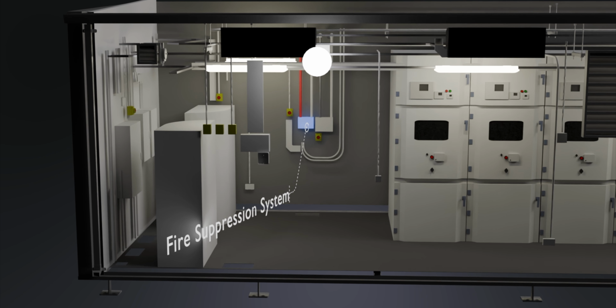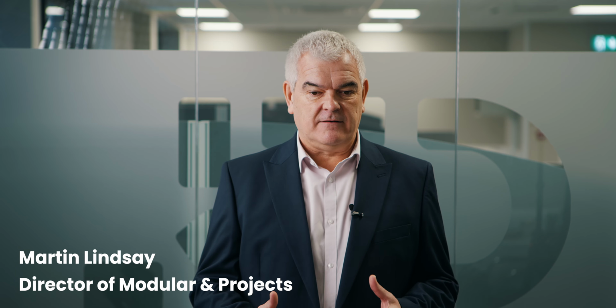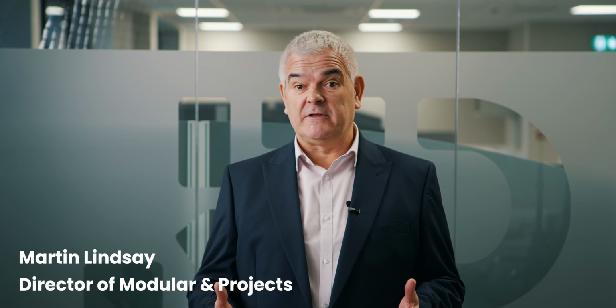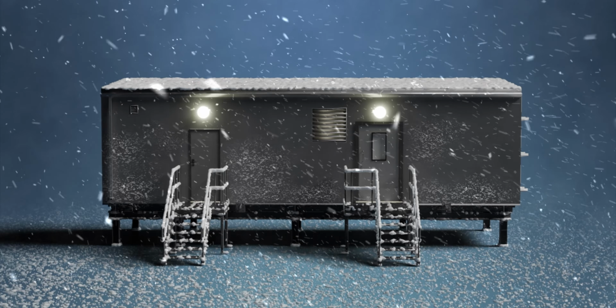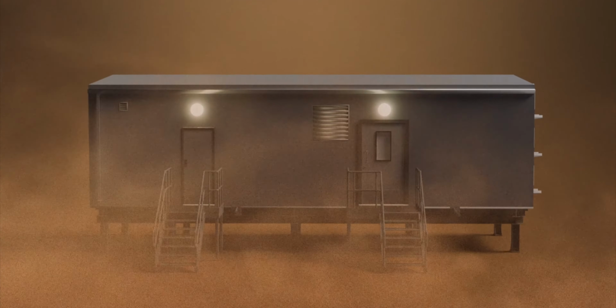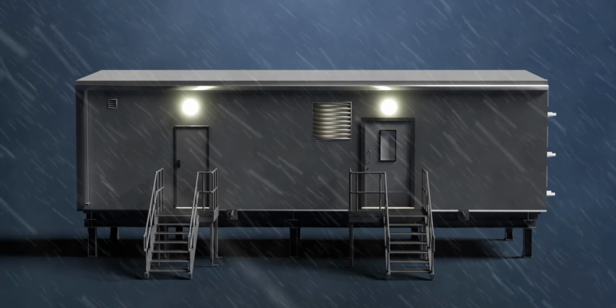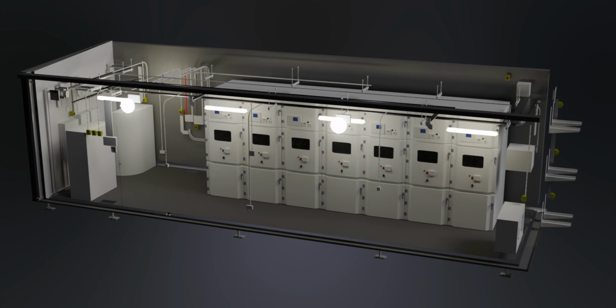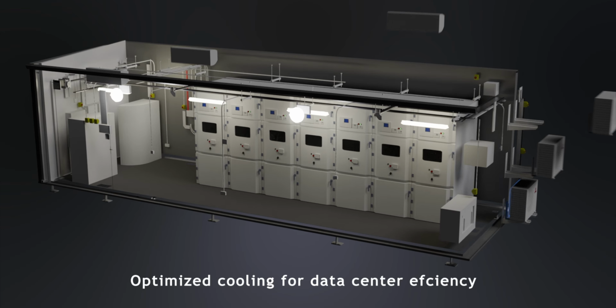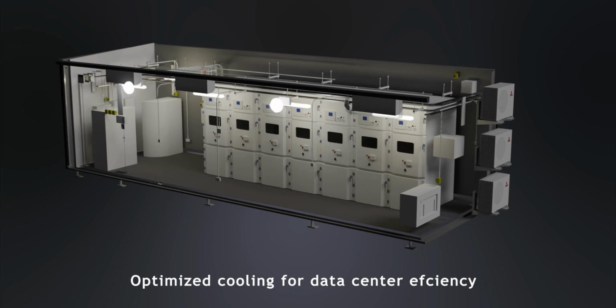So some of the considerations we have when designing a modular solution is to think about the environment that we're going to use that solution in. So what countries are going to be based, what's the temperature, what's the humidity, what are the conditions like. Free air mixed system will work well in lower temperature environments, typically Ireland, the UK. We go to somewhere hotter like Madrid or maybe Italy, we want to use a recirculation cooling.